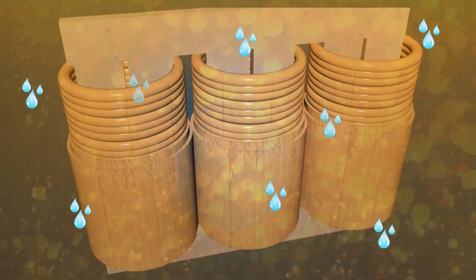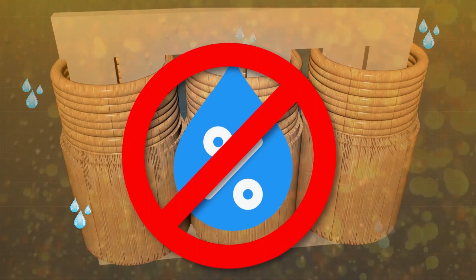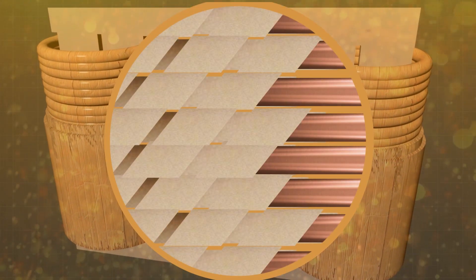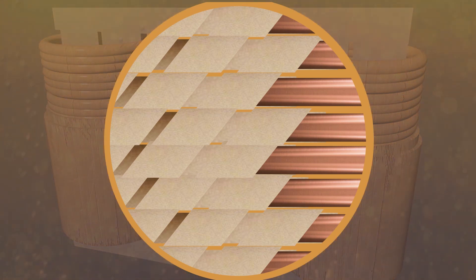The process removes water not only from the oil but also from the solid insulation. Therefore, this GlobeCore process facilitates keeping the water content in the solid insulation at a safe level, preventing cellulose breakdown.